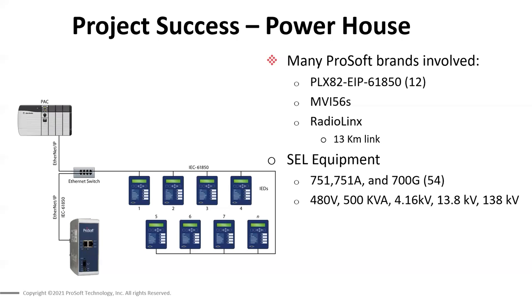On whether the two RJ45 jacks on the new module allow for building a ring network, not just parallel redundancy to downstream IEDs: PRP is the redundancy that most of the protective relays support with IEC 61850. They recommend having managed switches on the network to help control traffic. We didn't implement a two-port ring on the module itself — it is a true PRP, so it's either PRP mode or simplex mode.